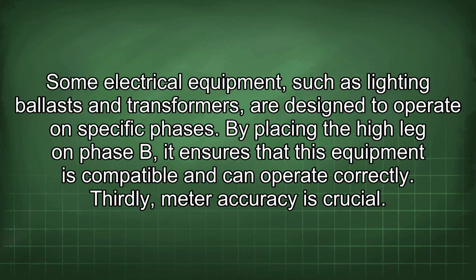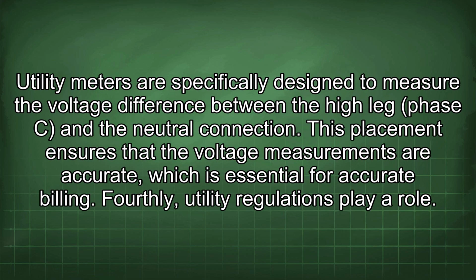Thirdly, meter accuracy is crucial. Utility meters are specifically designed to measure the voltage difference between the high leg phase C and the neutral connection. This placement ensures that the voltage measurements are accurate, which is essential for accurate billing.